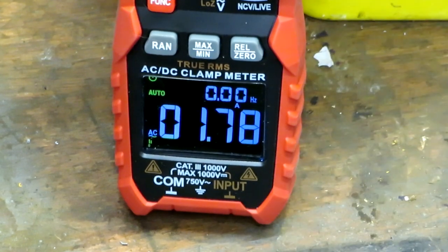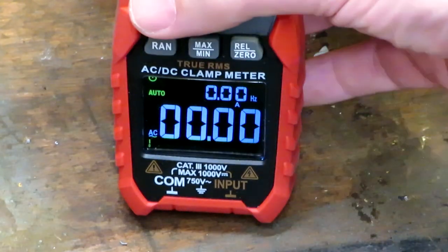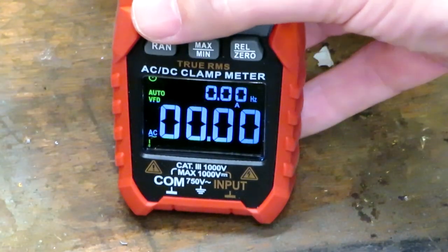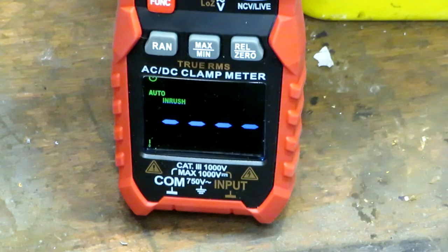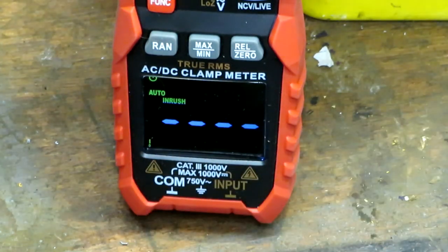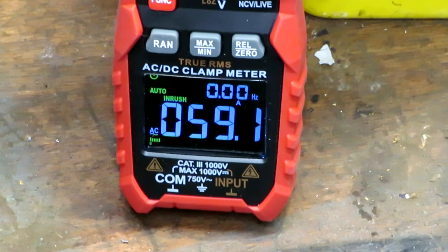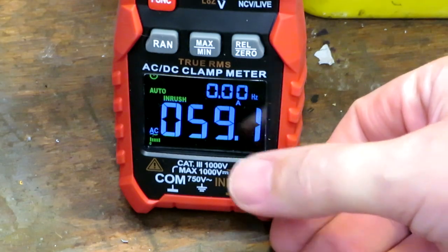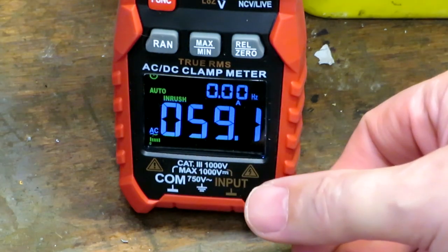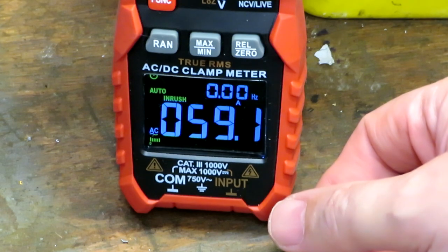So I'm going to switch it off. We've got to press a function switch to actually engage the inrush function. And we get all blanks here on the meter screen, so I'm going to switch back on. Hopefully you saw the lights flicker when I switched the transformer back on there, but you can actually see our inrush current, it's actually 59 amps. Wow, 59 amps, that's actually quite a lot of current, isn't it?